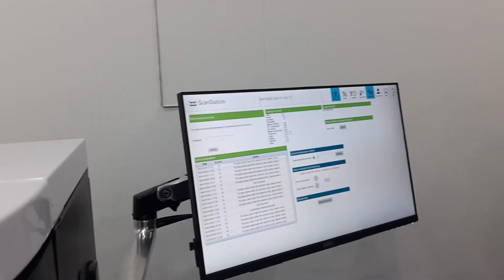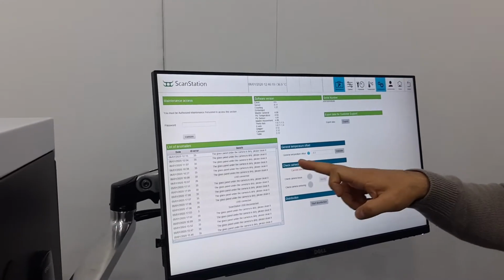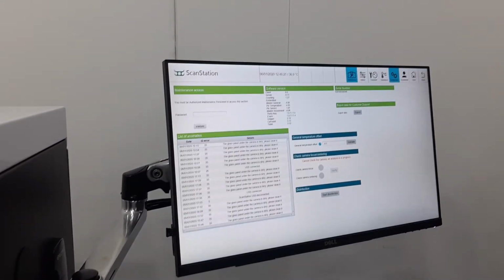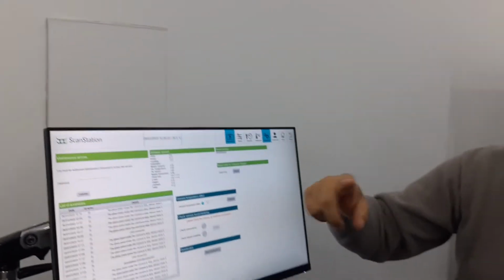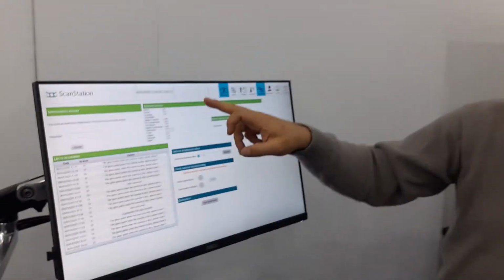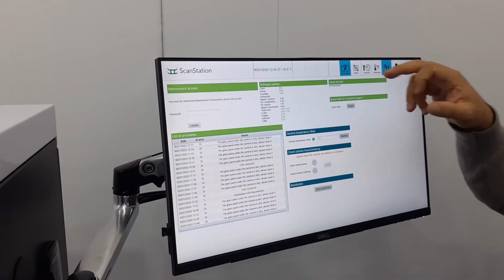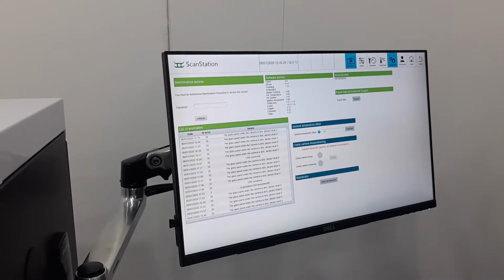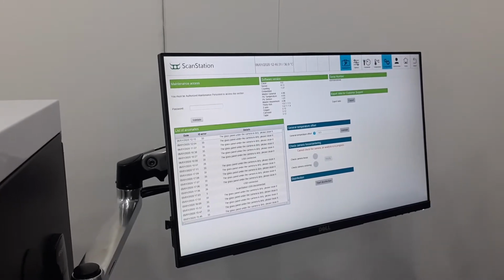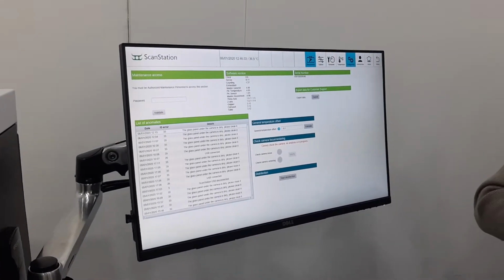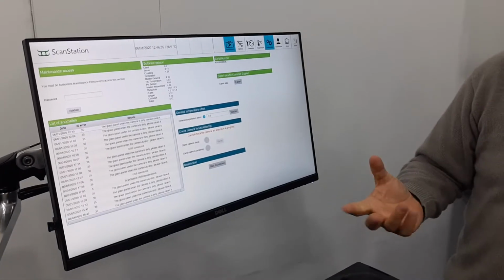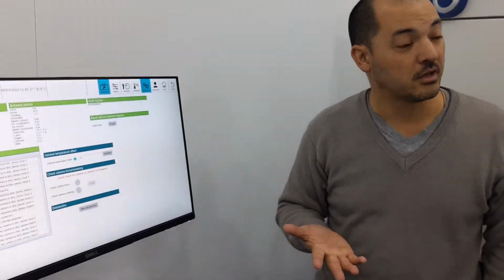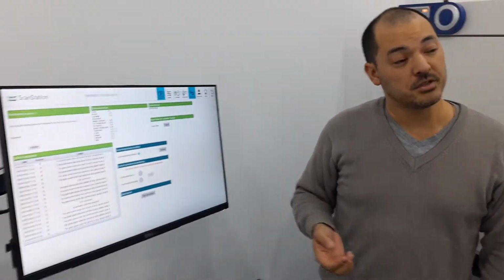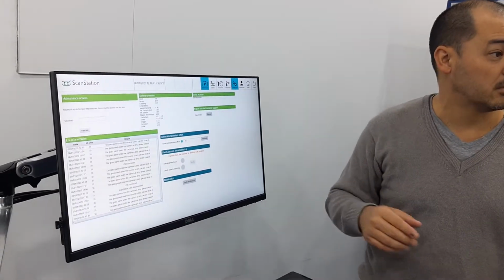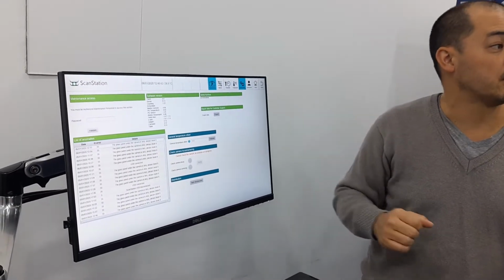So here anyway you have the list of errors. Also here you can change the temperature offset. So you see that the temperature, I asked for 37 degrees and here it's 36.9, so it's 0.1 degrees, so it's quite accurate. For example, every year you might do a calibration of the temperature. Maybe the temperature sensor is going to shift a little bit, like lose 1% every year.